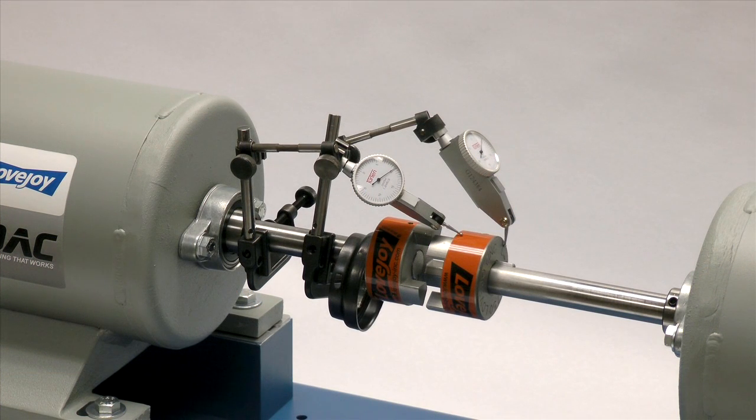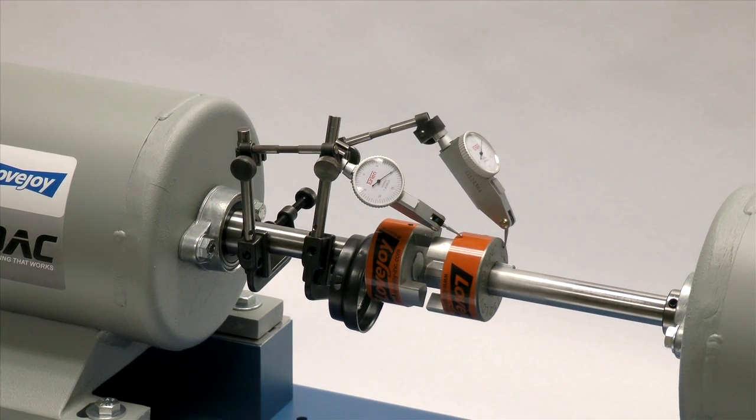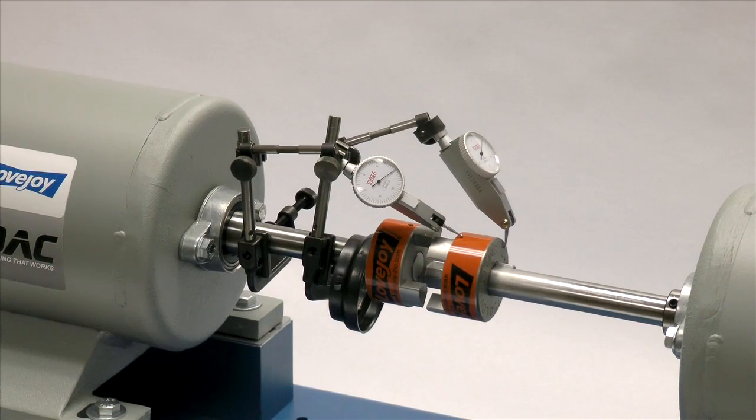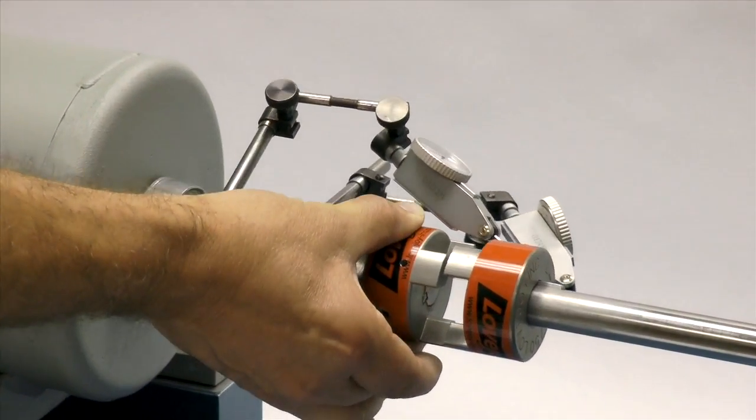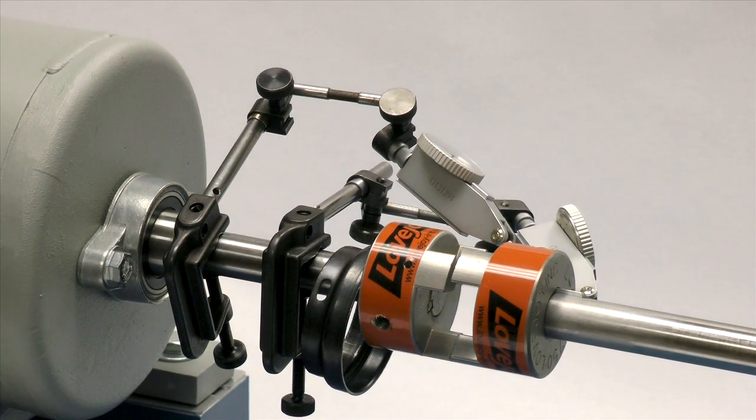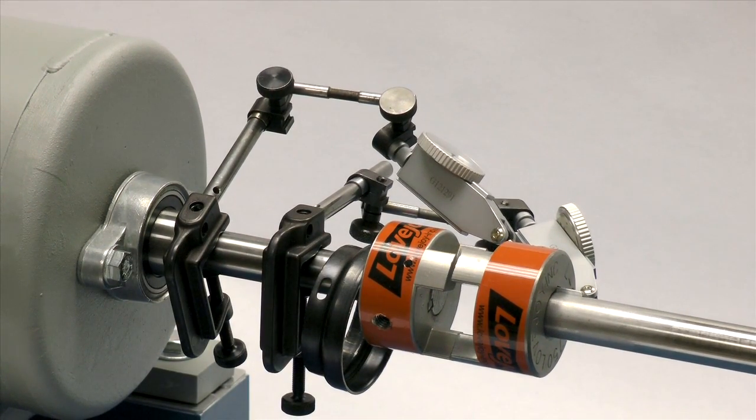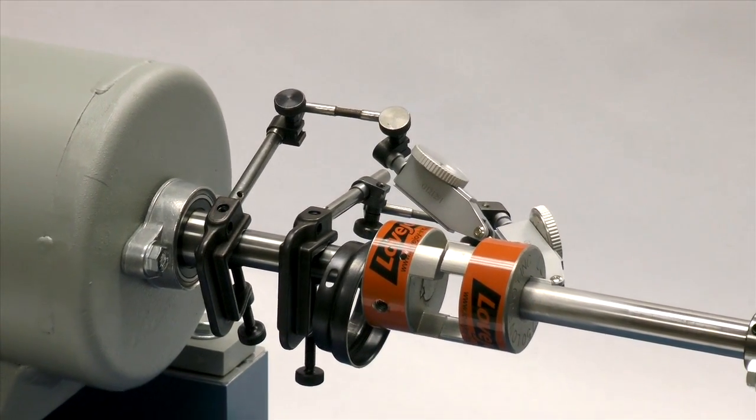If using a dial indicator, mount the indicator on the driver shaft with the sensor touching the hub on the opposite shaft. Rotate the shaft with the indicator to the 3 o'clock, 6 o'clock, 9 o'clock and 12 o'clock positions and make notes of the deviation on the dial. If this exceeds 0.015, fifteen thousandths of an inch, adjust the equipment to correct this condition.